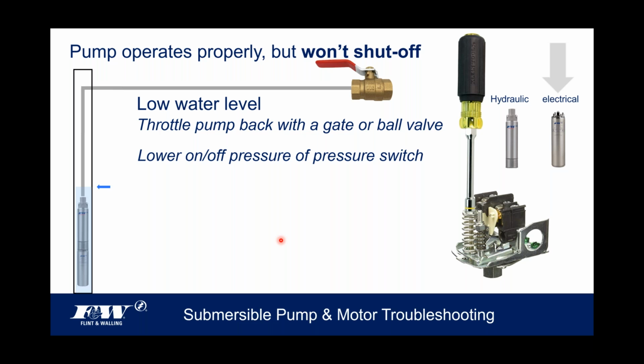Again, we talked about this in the previous slide. I always look at this process of lowering the pressure on a pressure switch, especially if the pump was functioning fine at that setting initially, and now over years it's not, as a band-aid, a way of just compensating for some of what's going on inside these impellers and diffusers. And you can lower that pressure switch down, and you can get that pump to cut off.